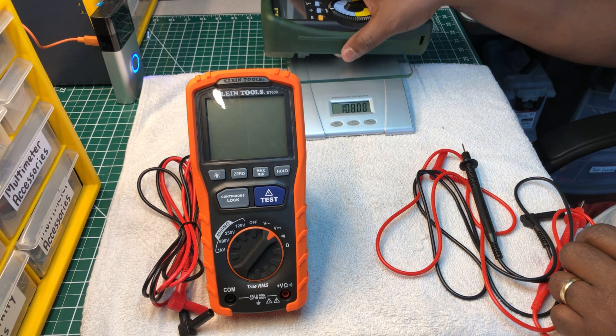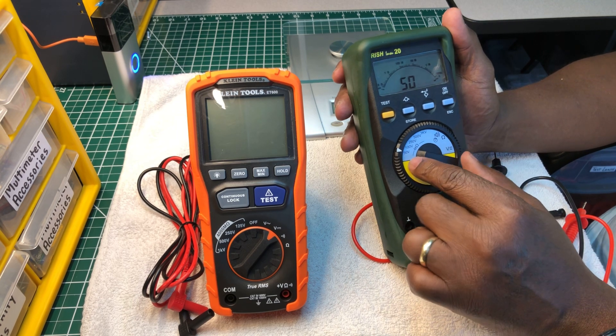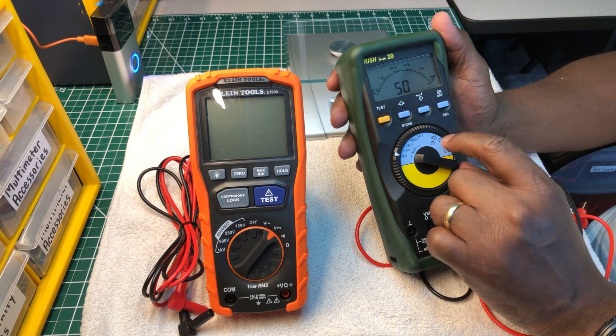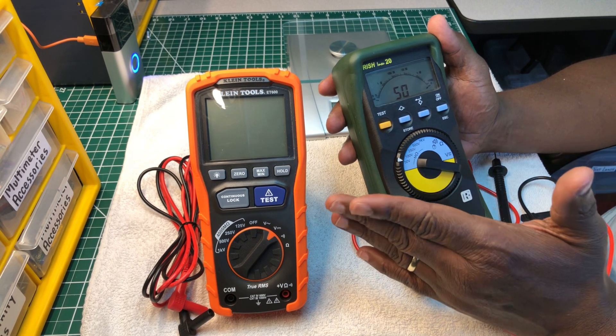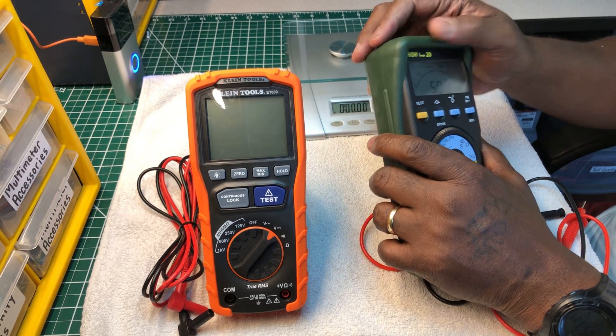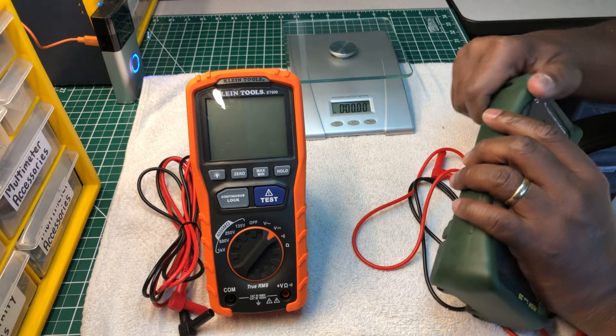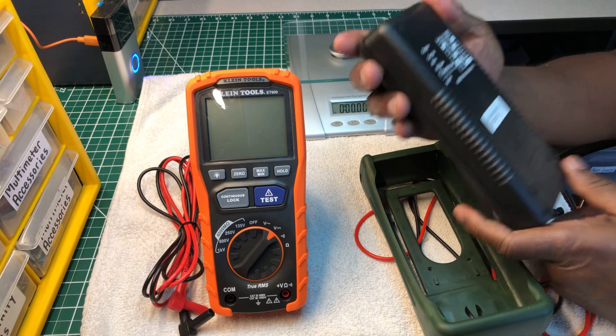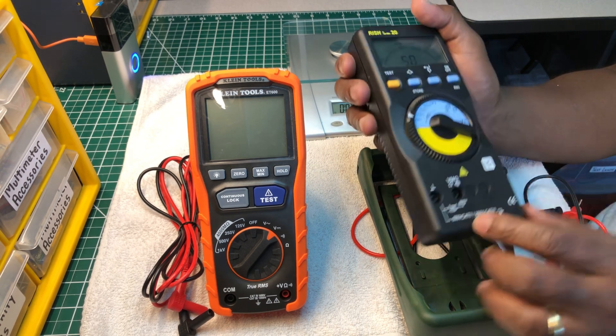This meter has features starting from the 50-volt range up to 1000 volts. It also has continuity, resistance, and AC/DC voltage. There's a time-set feature — I'm not sure what that's for — and a bar graph. It goes up to 10 gigaohms, which is a lot. However, I don't see any stamps from accredited testing labs — only a CE mark, which you see on a lot of meters and I don't put much weight on.